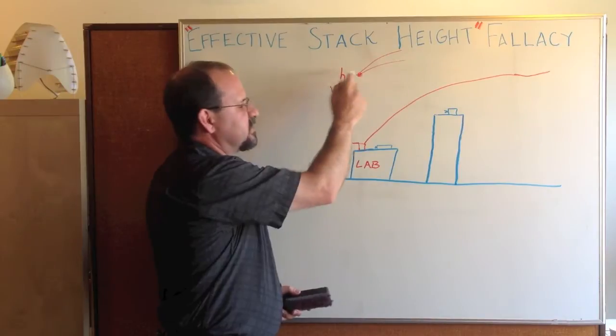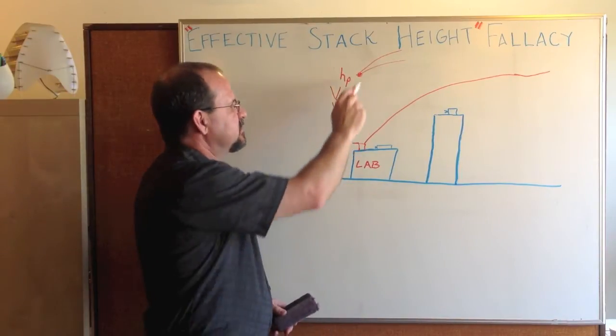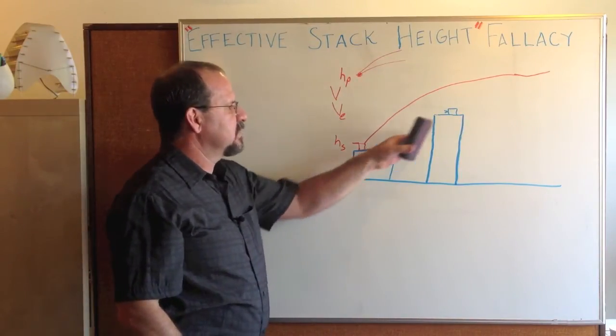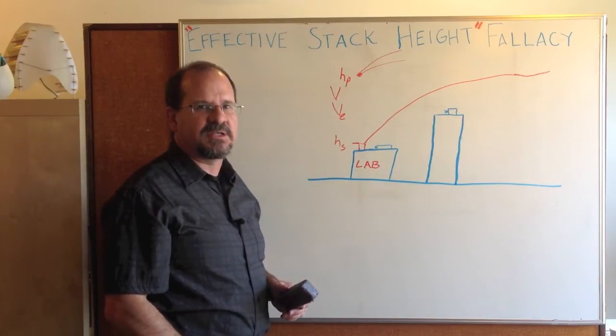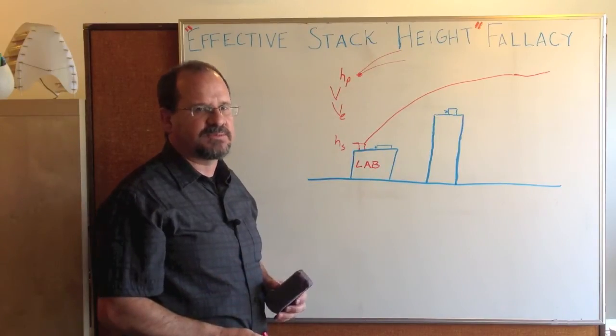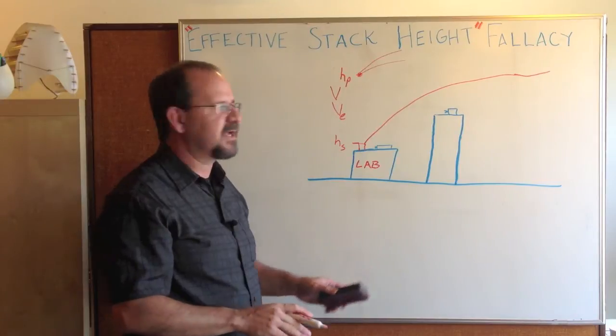The real risk in using that effective stack height is you're going to predict all that high plume rise and way underestimate re-entrainment and possibly have air quality problems. So forget effective stack height.